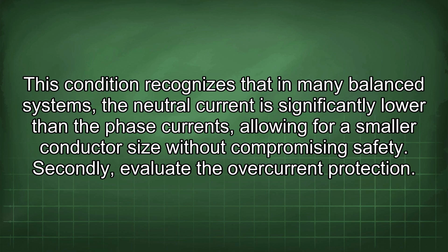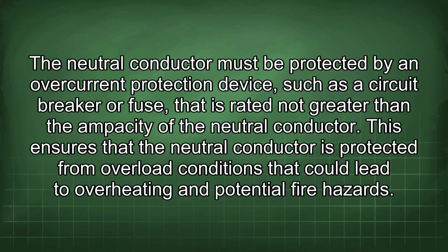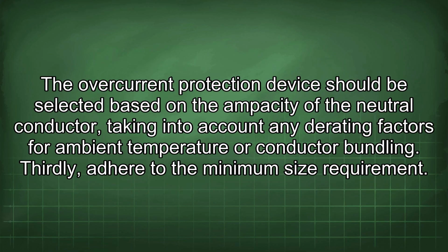Secondly, evaluate the overcurrent protection. The neutral conductor must be protected by an overcurrent protection device, such as a circuit breaker or fuse, that is rated not greater than the ampacity of the neutral conductor. This ensures that the neutral conductor is protected from overload conditions that could lead to overheating and potential fire hazards. The overcurrent protection device should be selected based on the ampacity of the neutral conductor, taking into account any derating factors for ambient temperature or conductor bundling.